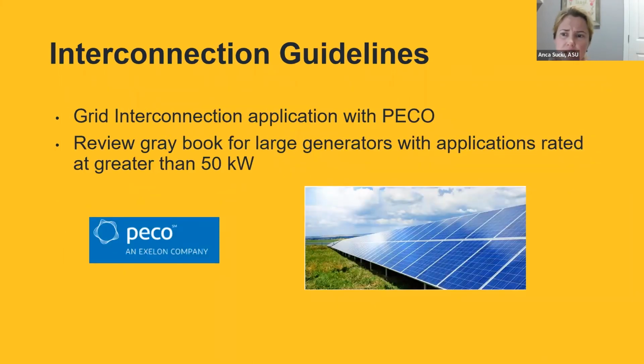Any renewable energy system connected to the utility grid will require written authorization from the local utility company, which is PECO, acknowledging and approving such connection. In order to make sure we follow guidelines for interconnection of generators to PECO's distribution system, we need to consult PECO's Gray Book. It is for large generators with applications rated at greater than 50 kilowatts. The Gray Book provides guidance to ensure that generators operated by customers connected to PECO's distribution lines will not impact the quality of service to other customers or jeopardize PECO's equipment.